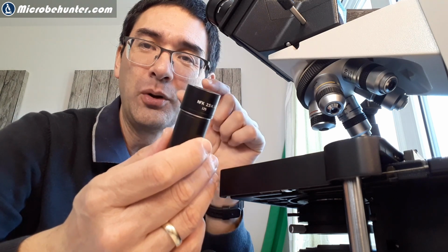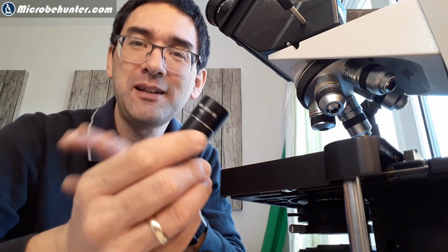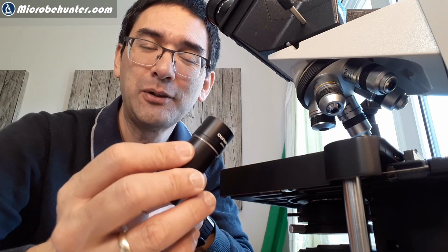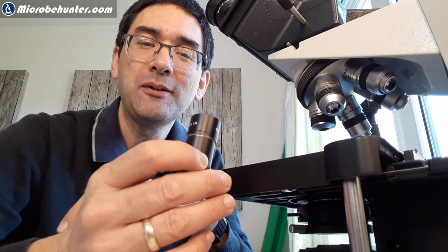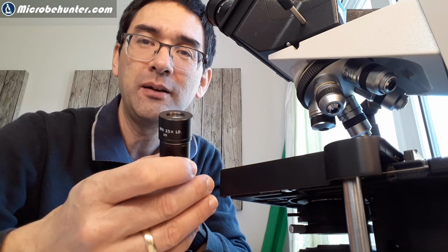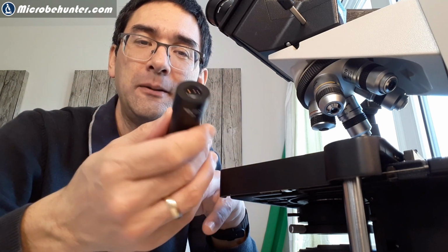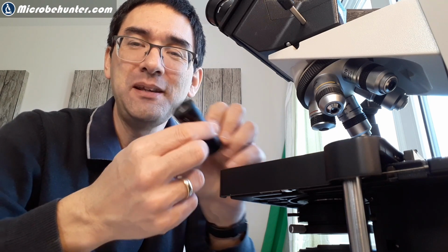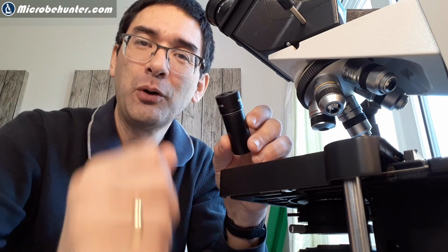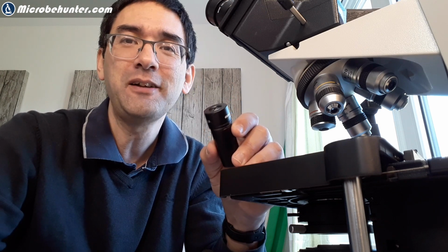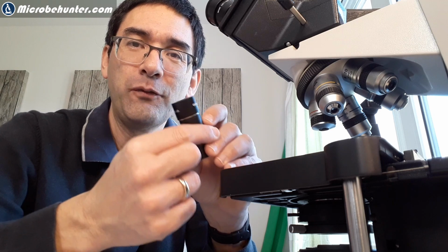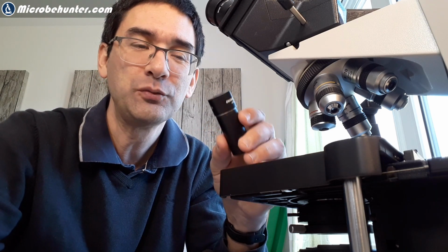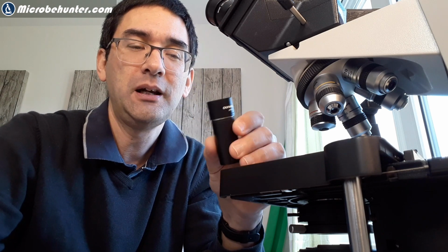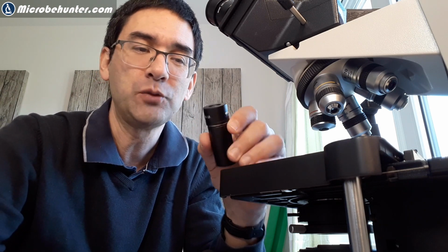But the modern camera sensors are actually much smaller than that, unless you have a so-called full frame single lens reflex camera. And this means that with this eyepiece, I'm actually getting a slightly higher magnification and a lower field of view than you would normally get. Now, I did look around for projection eyepieces that are also for smaller camera sensors, the so-called APS size sensors. And they are so expensive and so difficult to get that it's really not worth it. For the smaller sensor, you would have to pay around 600 euros just for this eyepiece because they're very rare and extremely expensive. So I said, forget about it. I'm just gonna work with this one.